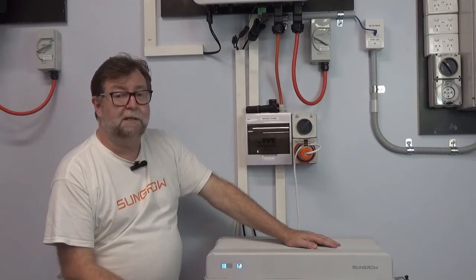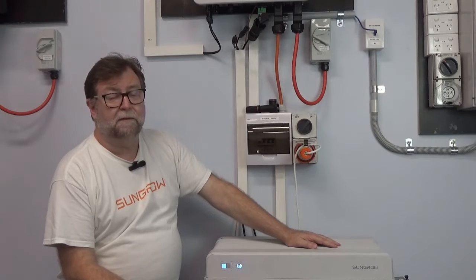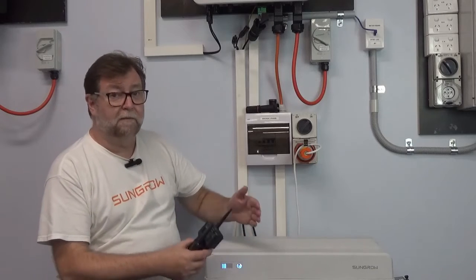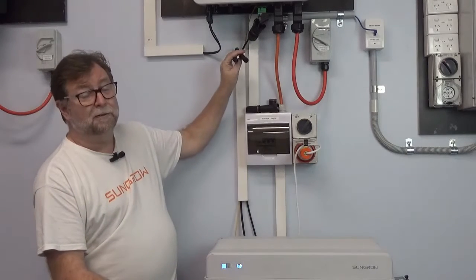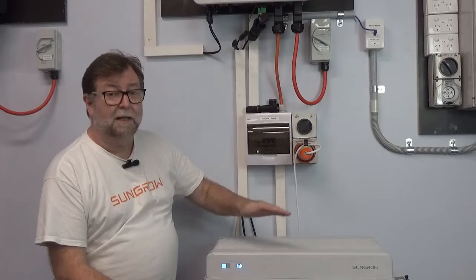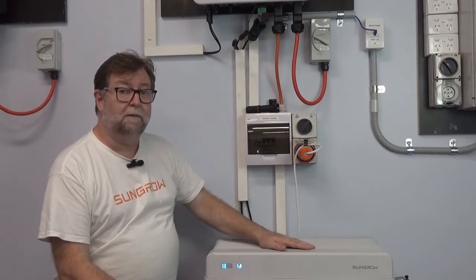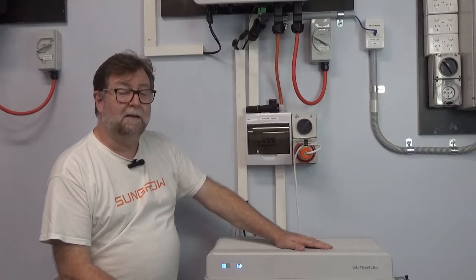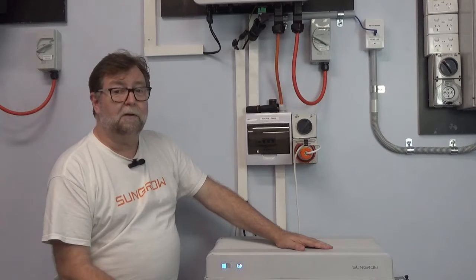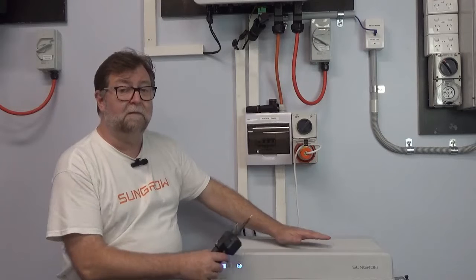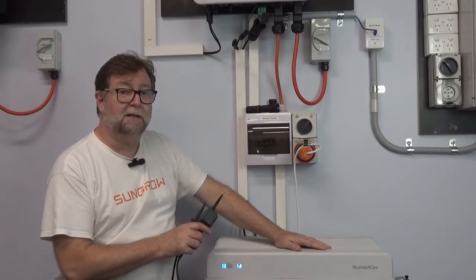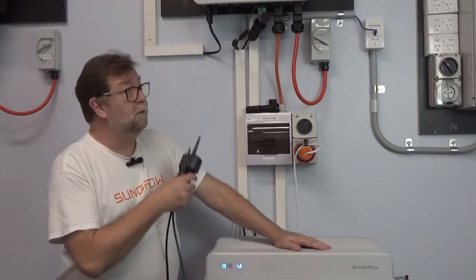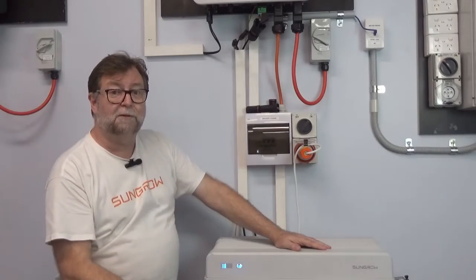In the following video I'm going to take you through the logic process for diagnosing if you think there's a fault in the battery. It's done in a reverse process. We start at the terminals here and work our way back. This is a good way to find if and where a fault occurs. This is information we need to process any warranty claims, so if you're doing a warranty claim we will need this information. Ideally you should take some photos of your measurements. Let's get started and we'll go from the top and work our way right down to module level.